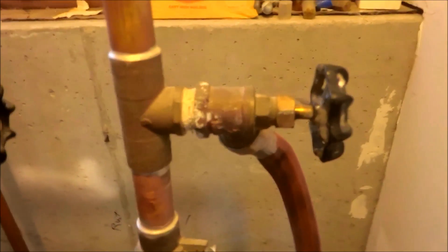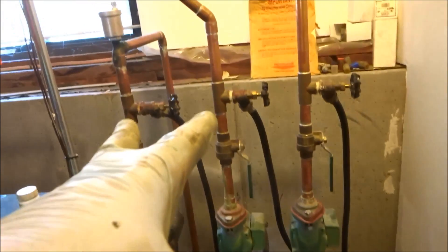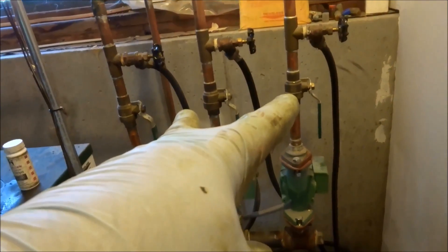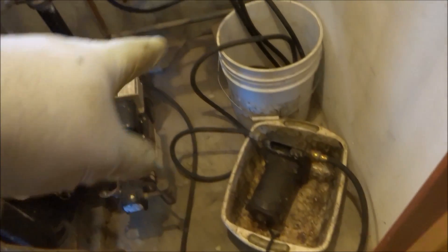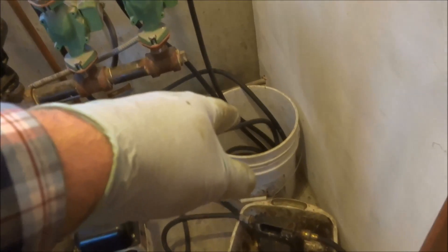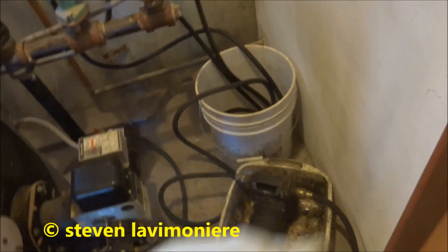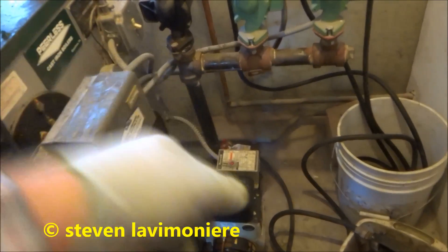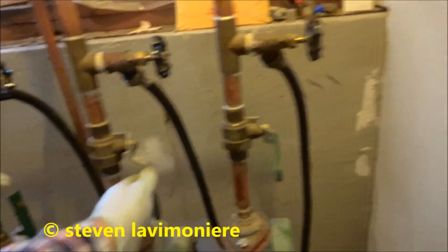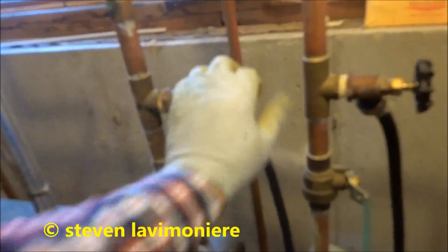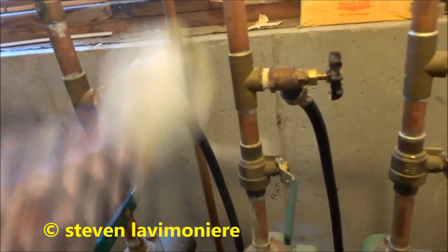I'm doing the last one here, flushing it. Alright guys I got it all drained out. I got three hose with one of my returns going into the bucket. I got this sucking out of that bucket and then going into the boiler drain in the bottom there. So I'll put antifreeze in there, suck out of that through this pump into the supply, into the boiler up the supply, back the return, get rid of the air right here. I'll do one at a time, leave one open for now and we'll do all the rest. So that's going to be my feed bucket right there.